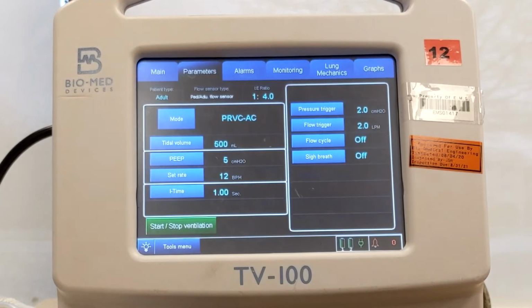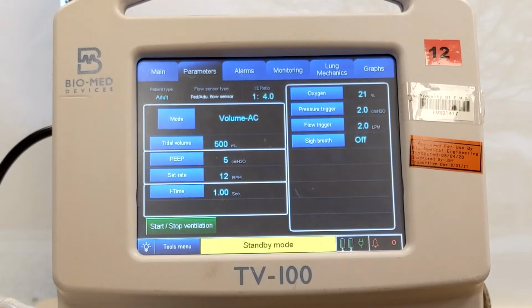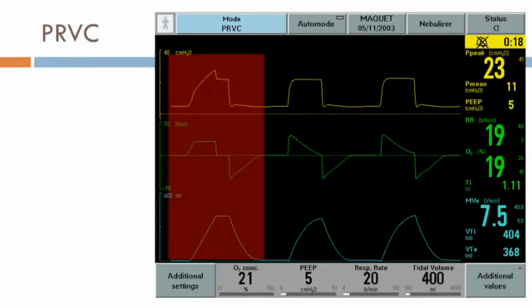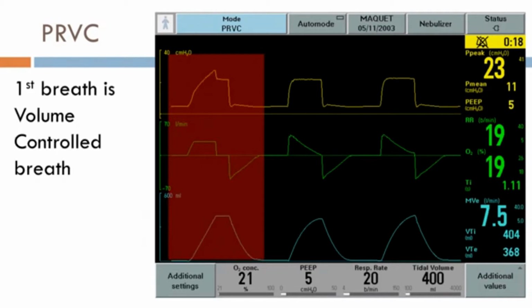In PRVC mode, we can see the parameters available are the same as what we would see in the volume assist control mode. So here's PRVC. The very first breath ever delivered by PRVC is actually a volume controlled breath. So you can see here that the flow is completely constant, affirming that this is a volume controlled breath. So the volume will increase up until this point, which is our desired volume of 400 milliliters.